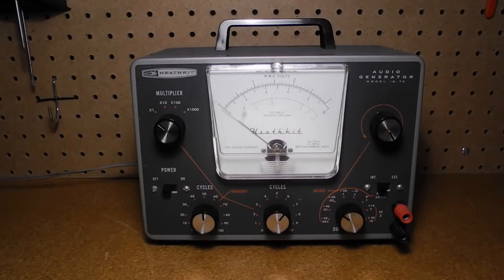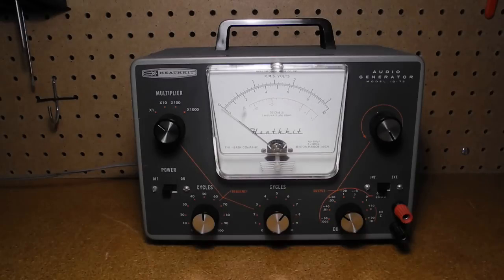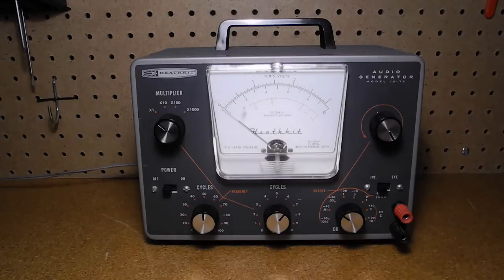The output frequency is selected by 3 knobs. There are knobs for tens and ones, which are multiplied by the multiplier switch, which supports ×1, ×10, ×100, and ×1000 ranges. For example, when the multiplier is set to 1, 10 set to 50, 1 set to 6, the generator will output 56 Hz. When the multiplier is set to 1000, 10 set to 20, and 1 set to 3, the output would be 23,000 Hz. The highest setting possible is 110,000 Hz, and lowest is 1 Hz, although it's only rated down to 10 Hz.